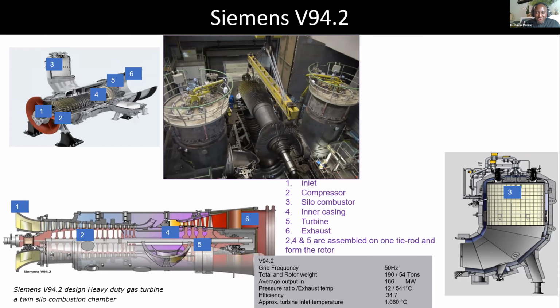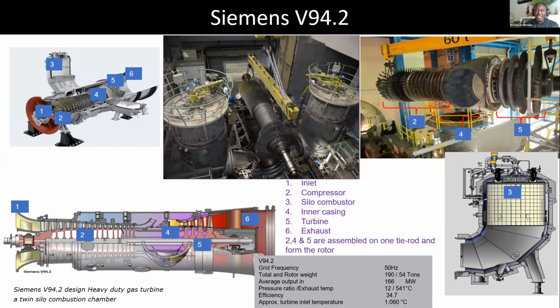And here, the rotor is tied by only one tie rod. So you see how the rotor looks. You don't have provision to split it, unlike the GE, where you can split the turbine parts. You see, these are the turbine parts, 1, 2, 3, 4 stages. This is the inner casing. This is the 16-stage compressor. For this, you cannot split it. You have to take it as a body. So you see, the crane capacity needed is about 60 tons. So you have to have that kind of capacity.